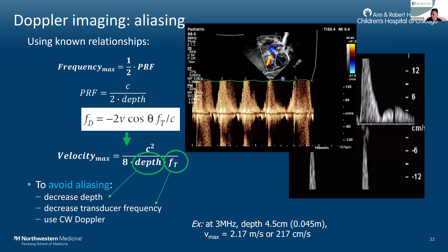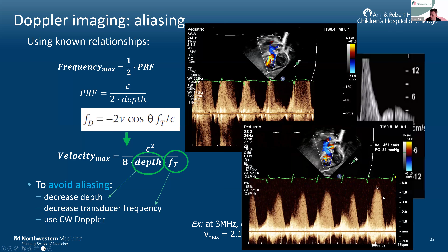We can thus show that to avoid aliasing, we can try to decrease the depth, decrease the transducer frequency, so either changing probe or changing the frequency at which a given transducer is emitting, or move to CW Doppler if location information is non-critical. And this is just an example of a case of a patient who has a VSD, where interrogation is first done by PW, and you can see the aliasing here. It looks like it's going negative, when of course that doesn't make sense physiologically. But when CW is used, you can see that there's no limitation to the maximal frequency shift or velocity that can be measured. And you can estimate a better accuracy of the pressure difference between the two chambers.